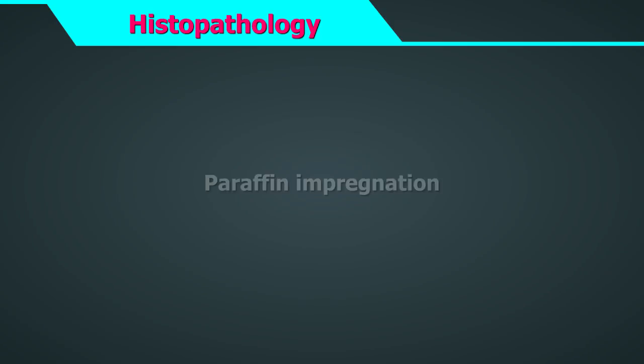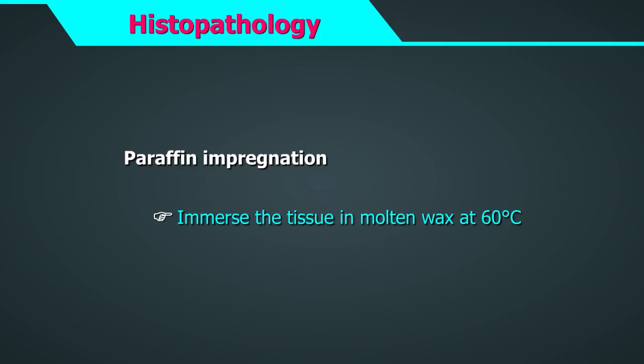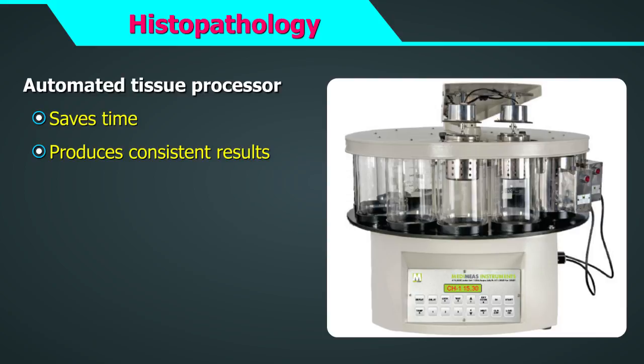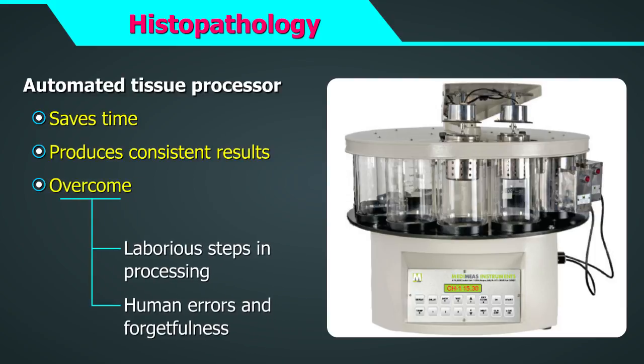Multiple changes of xylene may be required to clear the ethanol. The tissue is then immersed in molten wax at 60 degrees centigrade in a step called paraffin impregnation. In a large pathology laboratory, much of this tissue processing is automated to save time and produce consistent results. Automation overcomes laborious steps and reduces human errors and forgetfulness. However, the tissue processor should be maintained well. Processes for start-up and shutdown and details of solution change should be standardized, with work desk displays available.